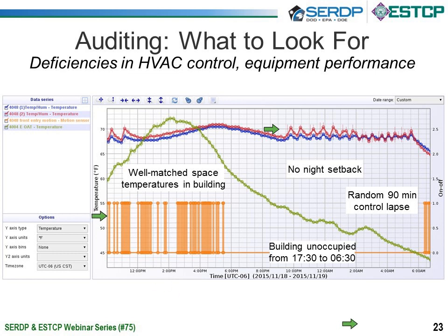These orange plots here are motion detection. So we're looking at when the last person leaves the building at night and when the first person comes in the morning, to understand what range of time is unoccupied and thus could potentially be set back. For this ESTCP project, we put in, I think, around 380 sensors on this 38th campus and got a very high-resolution look at all the buildings there to understand what is going on. The end result was seeing that we had basically no advanced controls set up in any of the buildings we were looking at. One of the buildings had a set of 7 different programmable thermostats, and of those 7, 2 were set up correctly, but the other 5 were either overridden or set up incorrectly. So overall, this is an example of a DoD building set which has no modern controls.